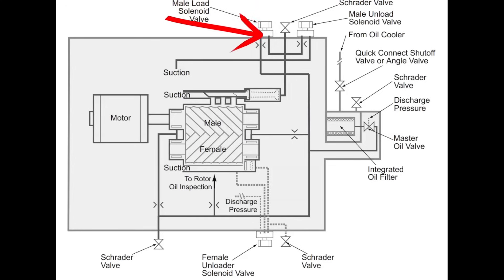But you'll hear the clicking. So when you're standing there by the compressor, you'll hear the occasional click, click, click. That clicking is this male, or it could be the unload, but it is these solenoids here getting activated. And we're just slowly bumping that slide bit by bit as it's going. So it's just making those small gradual movements. It only gets done once the compressor is started and ready to begin controlling based off a leaving water set point. We're past all of these startup safety checks and everything that needs to happen for a stable operation. We've established oil flow. All that's already happened.